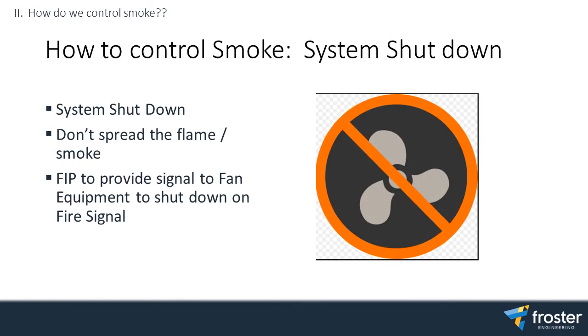System shutdown. So in one compartment, the strategy might just be to isolate the fan, so you're not spreading the fire, typically in a smaller compartment. The rule used to be a rule: anything over 1,000 liters a second, you're mandated to shut down. They've since changed that rule, so it's actually up to the design team. I don't really understand the logic behind that 1,000 liters a second in the first place.